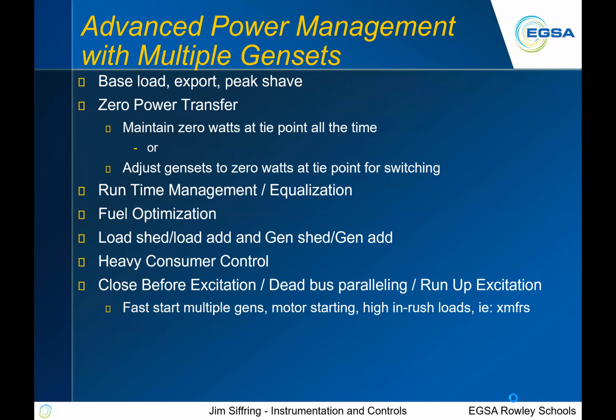So what's available with these advanced purpose power management systems, with multiple gensets? What can we do with them? With all these different controls, we can do base loading, we can export power, we can peak shave, and we can do zero power transfer, which I don't know if the switchgear guys talked about. Basically, at the tie point, you have zero watts between the two, or zero current flow, when you make the switch. You can do runtime management, equalization on gensets, and fuel optimization, cutting gensets out when they're not running in an efficient place.